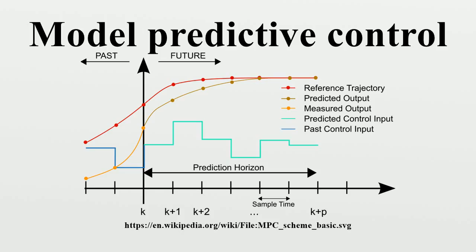These changes are calculated to hold the dependent variables close to target while honoring constraints on both independent and dependent variables. The MPC typically sends out only the first change in each independent variable to be implemented, and repeats the calculation when the next change is required.